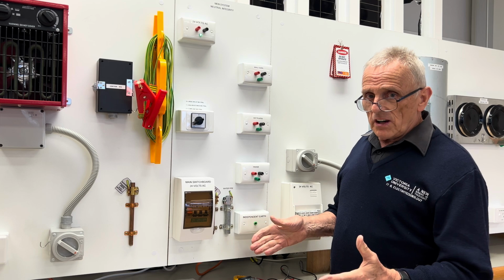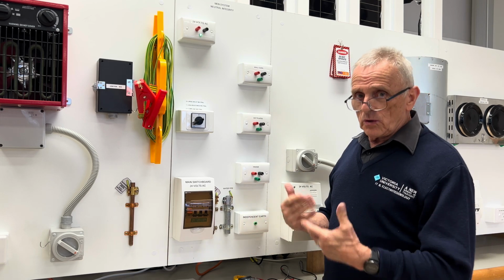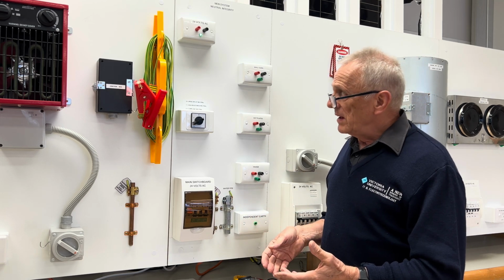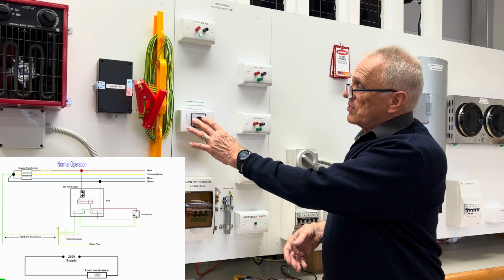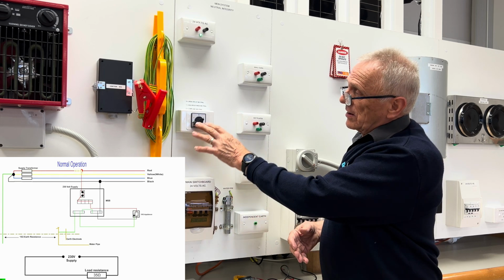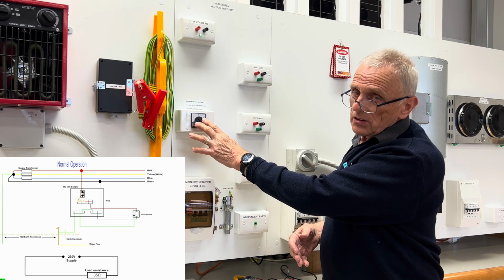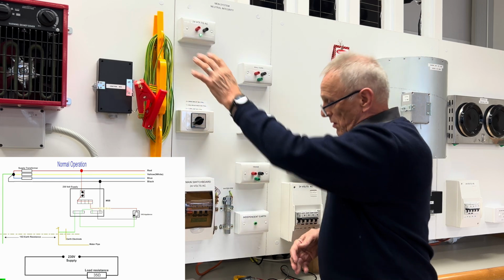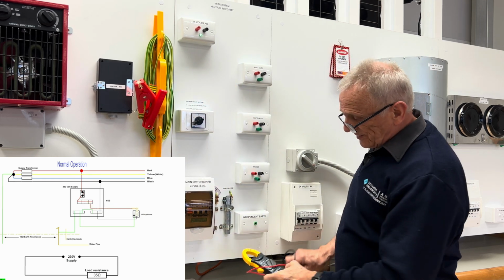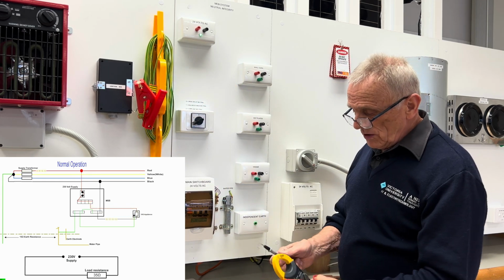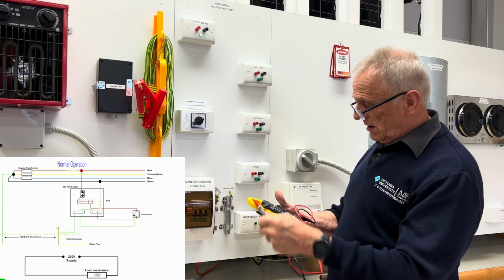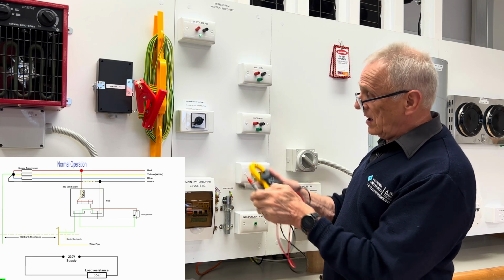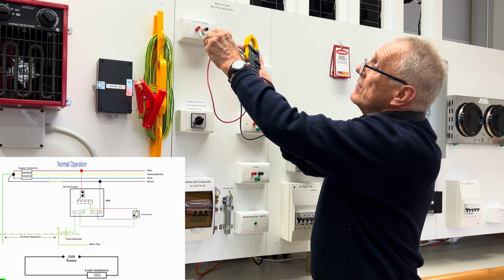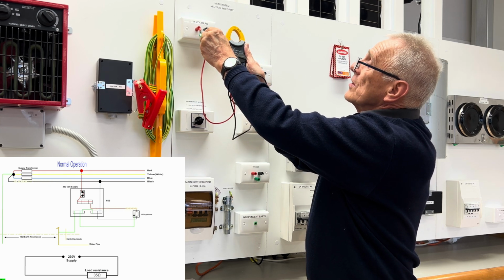The first scenario will reenact what a good installation should be. We have the switch set in a good neutral, a compliant neutral. We have our supply there. We take a measurement, and we're using extra low voltage, but the representation will tell us we have 24 volts or thereabouts.